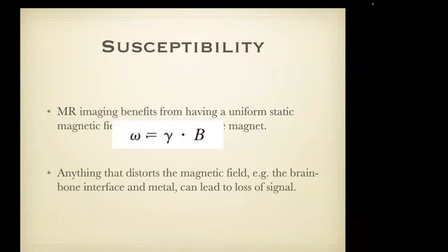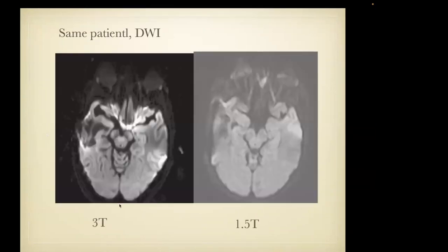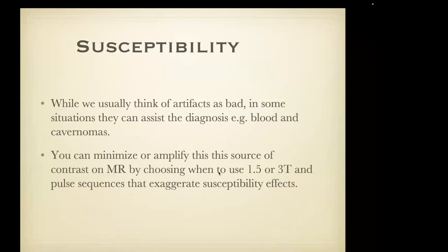If you can't see through the artifact on a fast spin echo T2 sequence — which has the least metal/susceptibility artifact — then none of the other pulse sequences will be of any benefit. Susceptibility artifacts are based on the need for a uniform static magnetic field. Remembering the Larmor equation: precessional frequency is proportional to the magnetic field. Anything that distorts the magnetic field — at the brain-bone interface and particularly with metal — will cause loss of signal. We can sometimes see things by maximizing susceptibility artifacts.